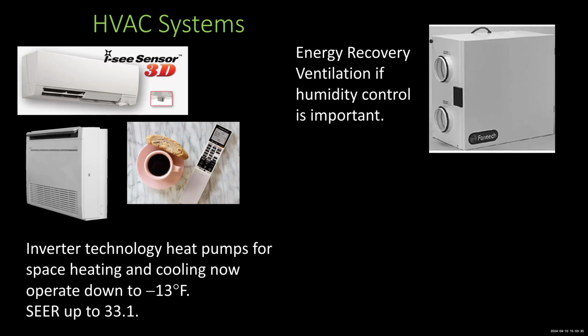Do a payback analysis. Here's another interesting creature called an energy recovery ventilation unit. Not sure whether you've heard of those or not, but what this does is it's a countercurrent heat exchanger, and it sucks in outside air to replace any inside air that might be vented out, say in a bathroom vent fan or a dryer vent or something like that. And if that outside air is hot and humid, and in fact, it's replacing the indoor relatively cool and dry air with hot and humid air, then that indoor dry air going back outside alongside of the outdoor humid air also does some dehumidification. So therefore you need a condensate drain on this thing.